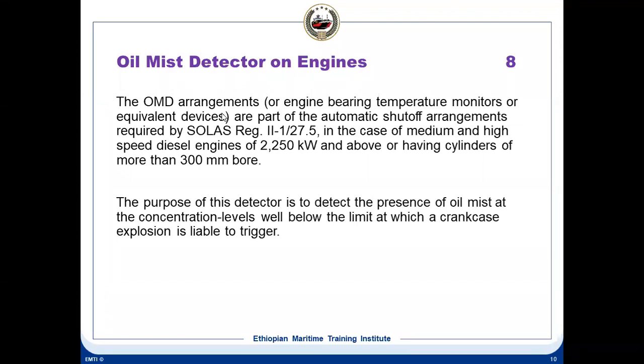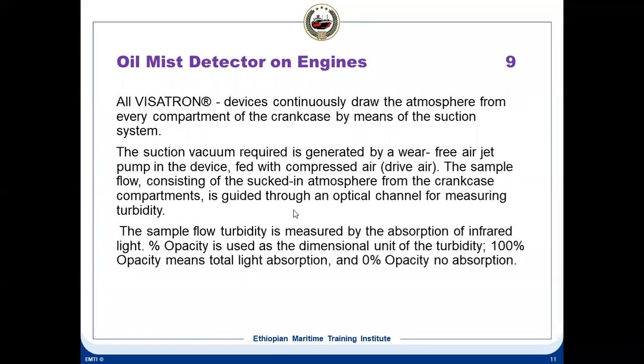And this is on the main engines. This oil mist also can cause a crankcase explosion. That is why on the engine you will find this. Mostly you will find the Visatron types, Visatrons. It is continuously drawing the atmosphere from every compartment of the crankcase. Normally you must have seen there is a fan inside on the top, and there is a rotary valve. So it is shifting every unit, and the fan draws the air from inside.